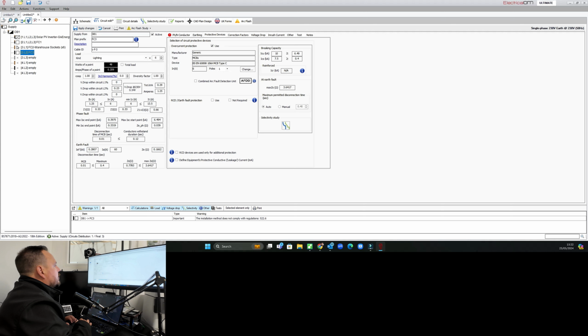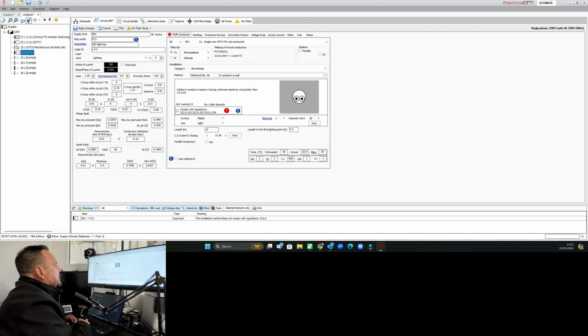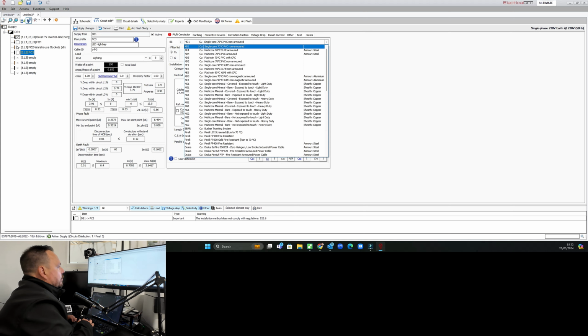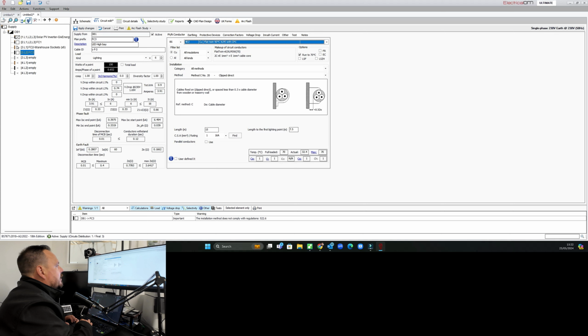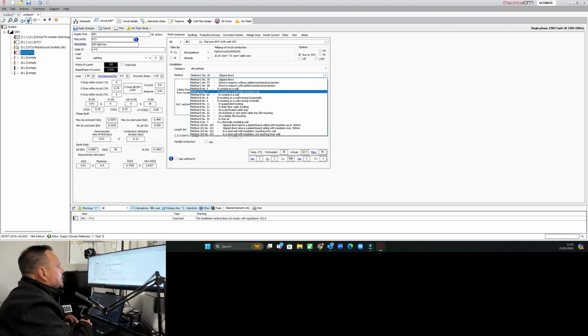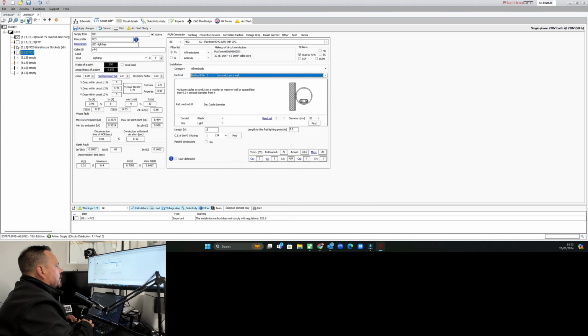48 watt fittings, so we can pop those on there. And again, we'll just put that down as LED high bay. In fact, we'll change it to a bit of a better example and pop them at 150s. Why not? So the phase neutral conductor on these ones, we're going to go for, again, just the twin and earth 90 degree XLPE. And again, we'll do it in conduit, because why not? It affects the values a bit better in conduit on a wall.